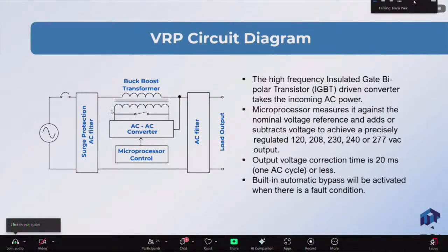So then, it's protected and cleaned AC power, but voltage is still bad here. So we go through a buck boost transformer. This is a little isolation transformer with 20% capacity of full output power. For example, if the load was 10 kVA total, we would only use a 2 kVA buck boost transformer. We could still add 20% or subtract 20% from the voltage with this technology. What we do is we take some of this power, up to 20% of the incoming power, and use an AC to AC chopper converter with a microprocessor control.